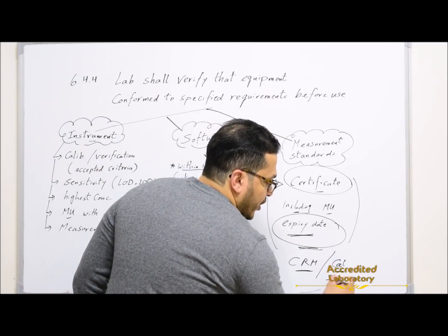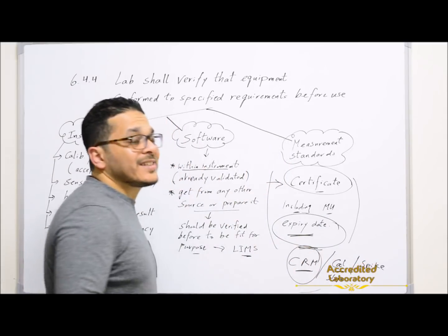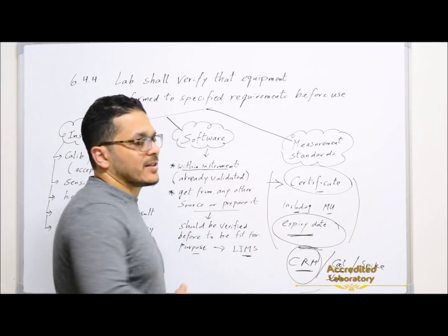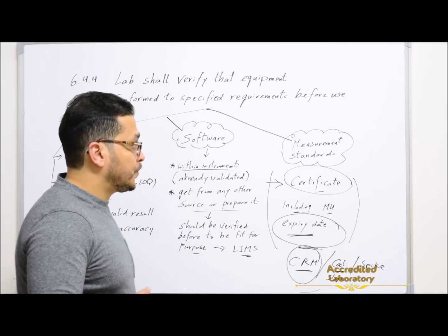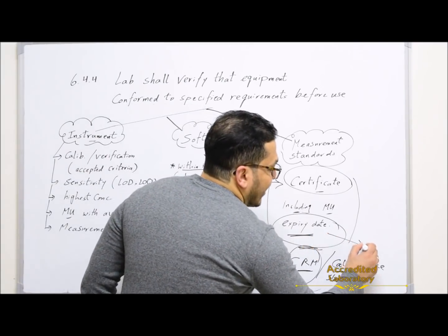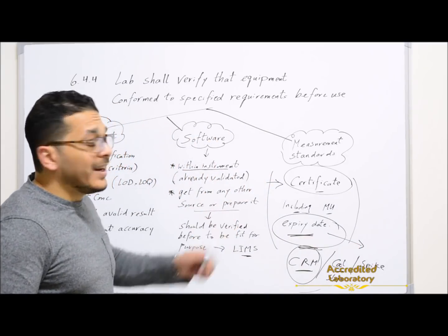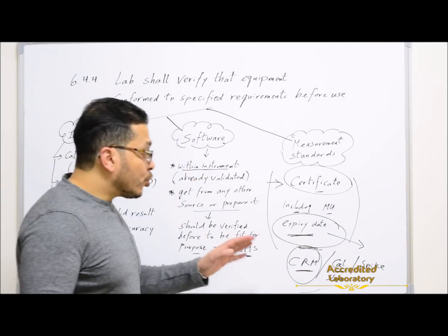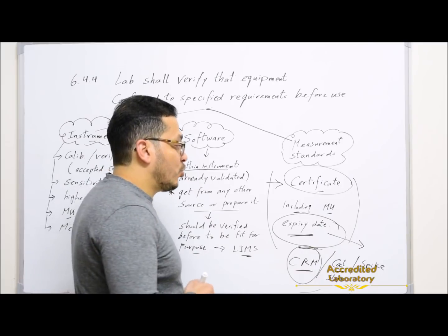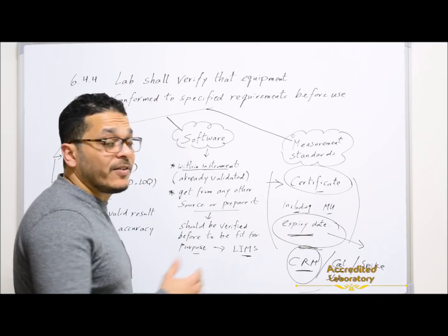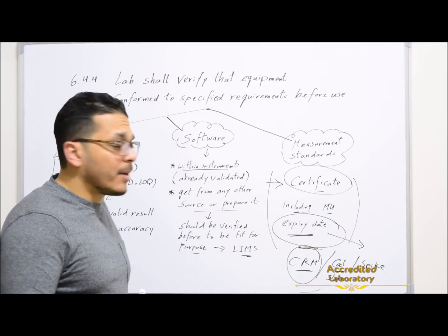from the calibration curve, the slope of calibration, and from spike samples. But the most important point is using CRM to ensure that these standards are accepted and can be used to get accurate and reliable results. After the expiry date, you can extend the period of validity of this measurement standard also by CRM or PT. You should use only CRM or PT to verify that these standards are still valid, and can be used to get accurate and reliable results.